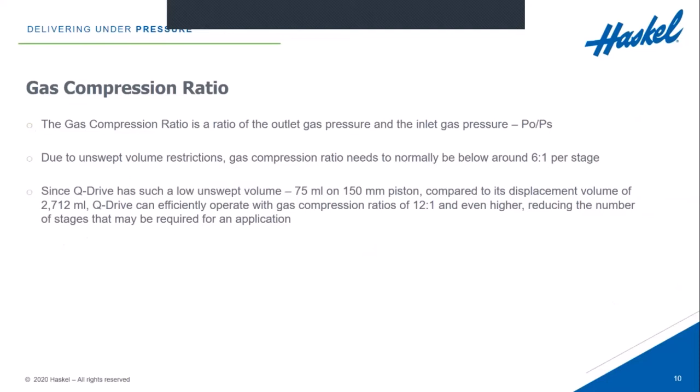The gas compression ratio is calculated by taking the desired outlet pressure and dividing it by the gas supply pressure. Due to unswept volume restrictions, in most gas Haskell boosters, we try to keep that number around six to one, sometimes a little higher, sometimes lower. We try to target around five or six to one.